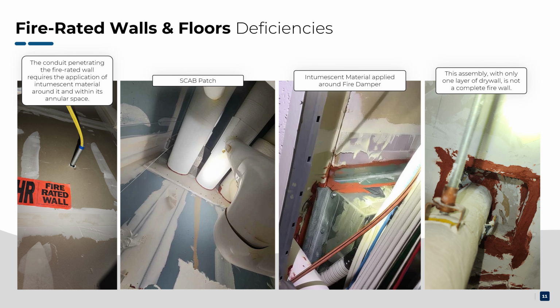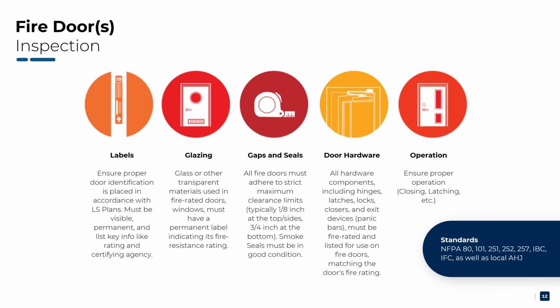What would life safety look for in our department, say, in corridors or rooms? We can start with fire-rated doors. Their purpose, as we know, is to slow the spread of fire and create a safe zone for patients and staff. Beyond just making sure they open and close, there's a lot to inspect. All the door hardware must be free of damage and function properly. The gaps between door panels and around the door have to meet strict maximum clearance limits.